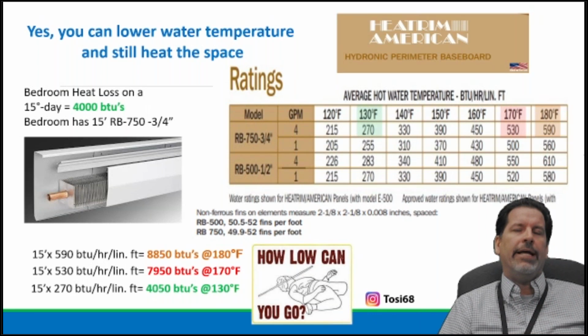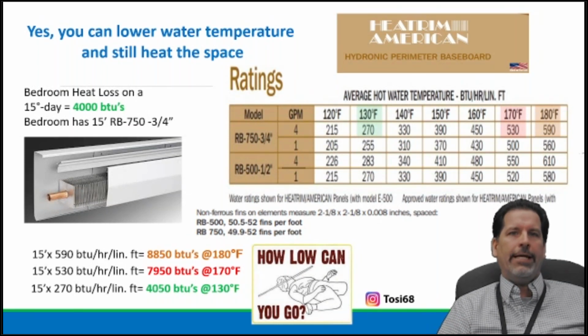Now look at the chart. It's not 590, it's 530 BTUs per lineal foot. So, okay, we got a little better. We're not at 8,900, we're at 8,000 now. We're still twice as many BTUs required for that bedroom. There is no control in that bedroom, right? Typically in a high ranch, the thermostat is in the center hall. So what is that thermostat doing? And that bedroom now is overheating. People are perhaps opening some windows, so we're going in the opposite direction.